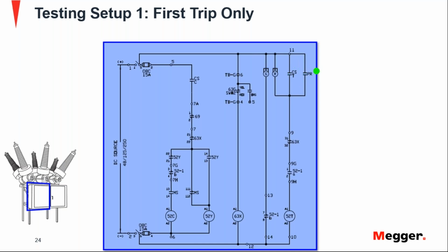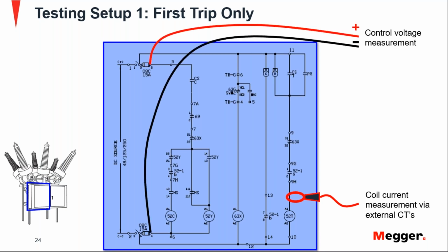So this operation, or the operation of the circuit breaker, will be commanded from the control room. In this case, the command is not going to come from the instrument. So we don't need to do any actual connection to the trip coils or to apply a signal to this circuit. The signal is going to come from the relay from the control room. So the very first connection is a CT that is going to monitor the current in this circuit. Then we want to monitor the voltage.